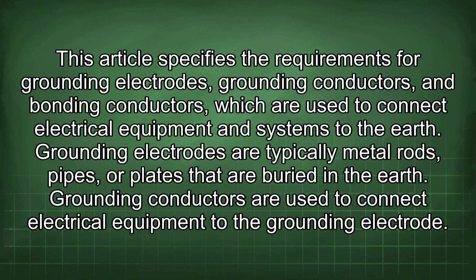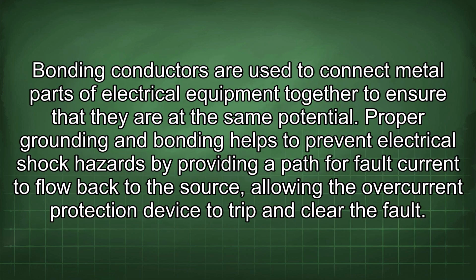Grounding electrodes are typically metal rods, pipes, or plates that are buried in the earth. Grounding conductors are used to connect electrical equipment to the grounding electrode. Bonding conductors are used to connect metal parts of electrical equipment together to ensure that they are at the same potential. Proper grounding and bonding helps to prevent electrical shock hazards by providing a path for fault current to flow back to the source, allowing the overcurrent protection device to trip and clear the fault.